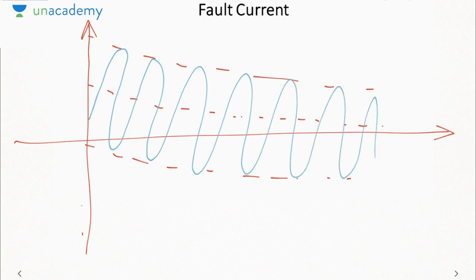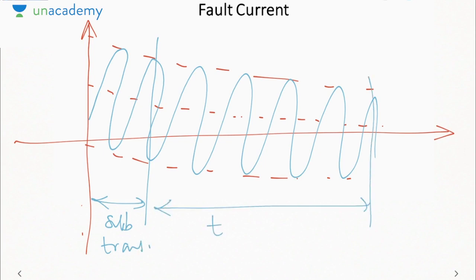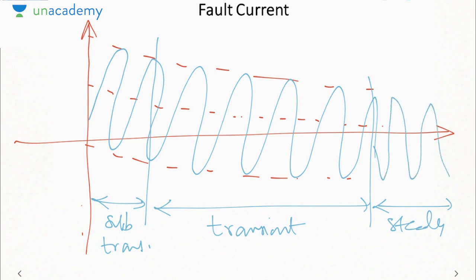Okay. I have shifted it upwards by an amount, the DC offset current. So now if you see, it is not symmetrical above and below the x-axis. Now the initial 1 or 2 cycles of the fault current is called the subtransient period. Then some more cycles, 3 to 5 cycles, is called the transient period. And once the DC offset current is almost 0 and the steady state current settles down, it will be called the steady state period. Then the waveform will be symmetrical about the x-axis, because the transient would be decaying to 0.